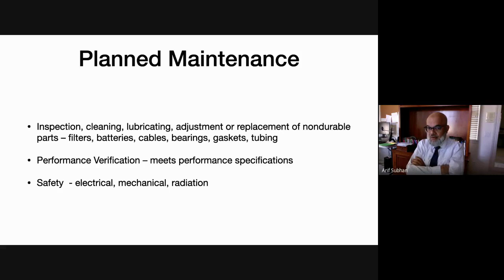They do that. Also, as I mentioned, performance verification, that's the component where you're making sure that it's delivering the right output, measuring the right rate, etc., and meeting the performance specification. Safety aspects we talked about earlier too: electrical safety, mechanical, and if it's a radiation emitting device, is the radiation that's coming out of the device safe within the limits or not?